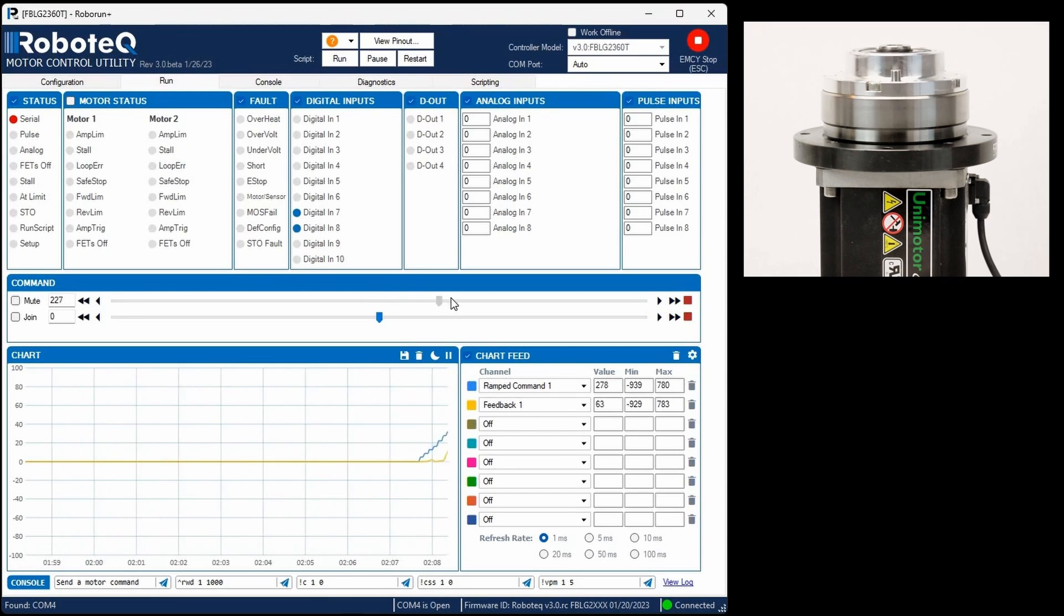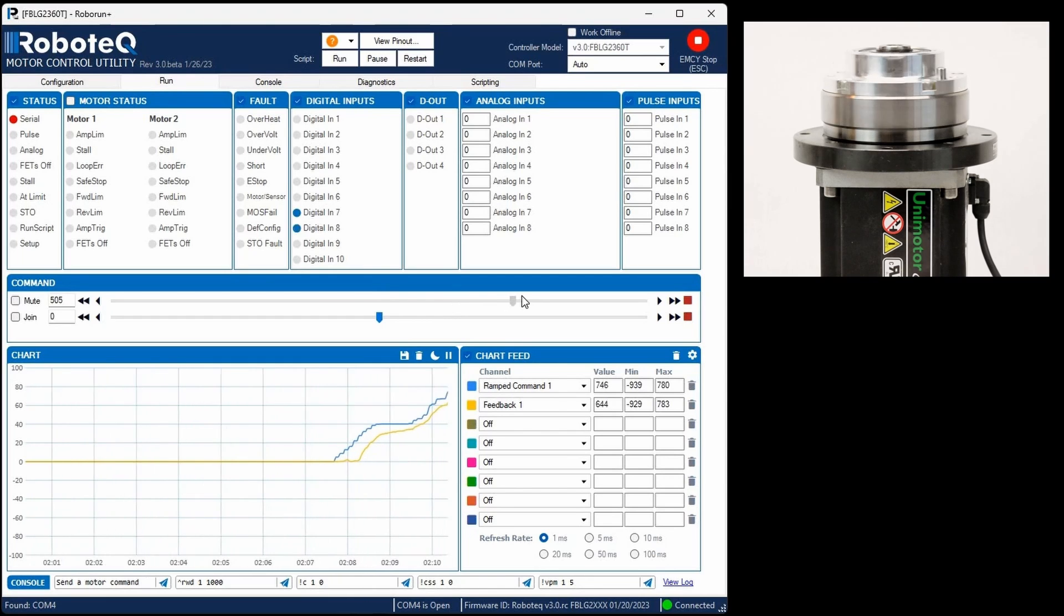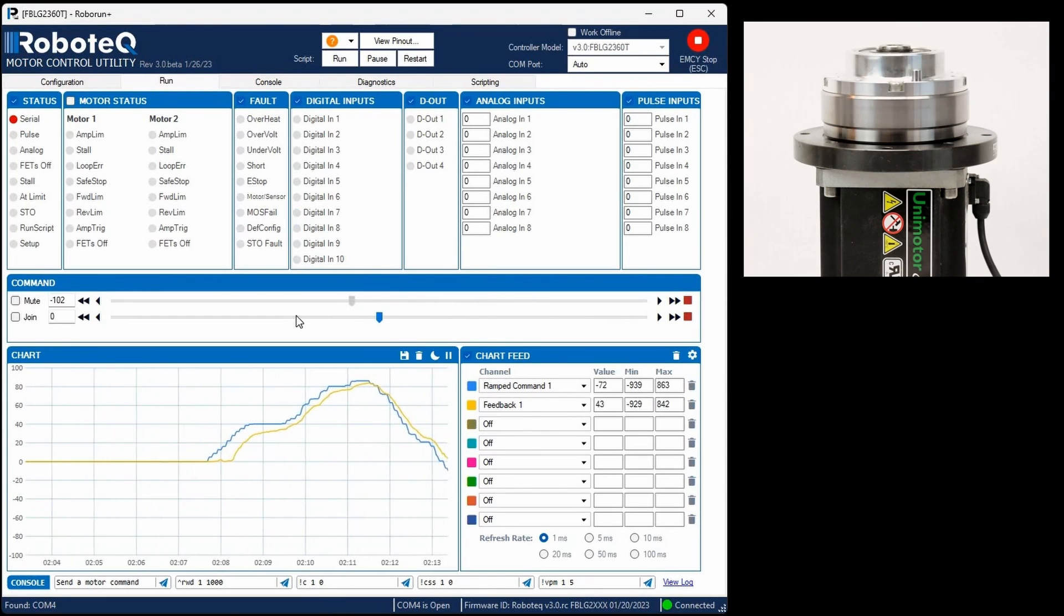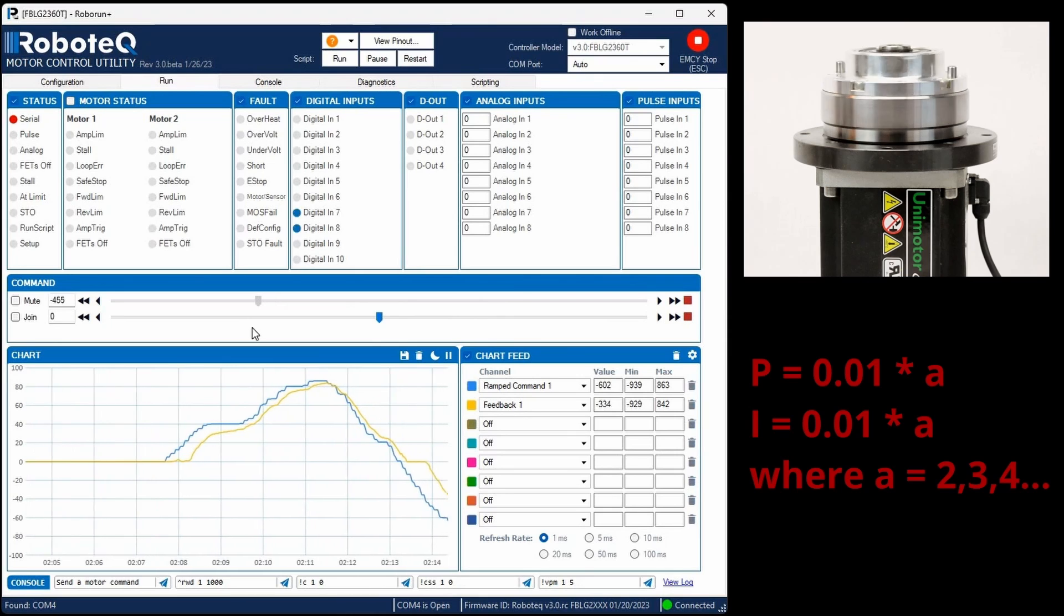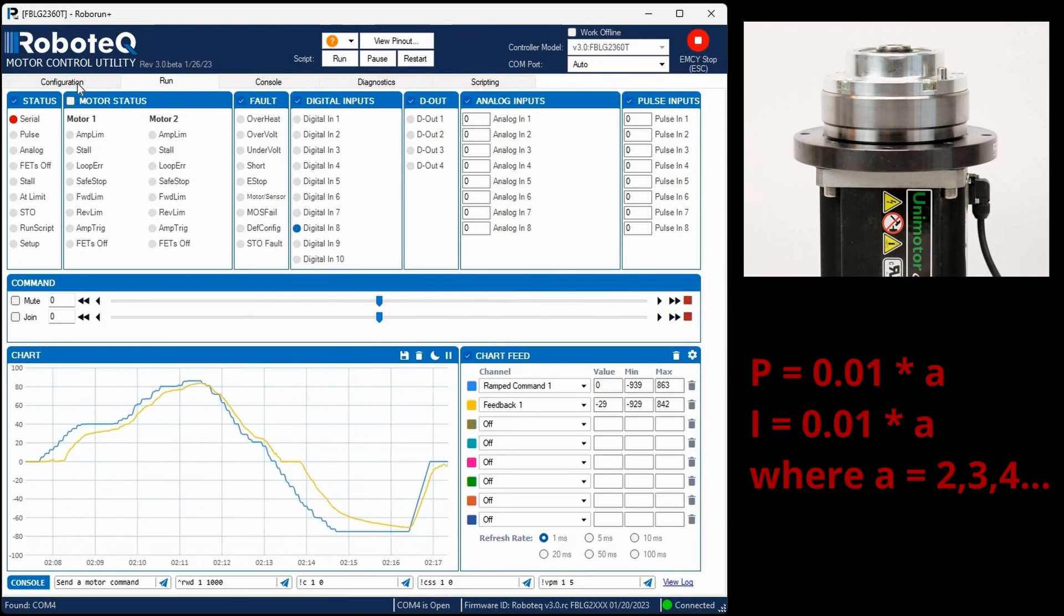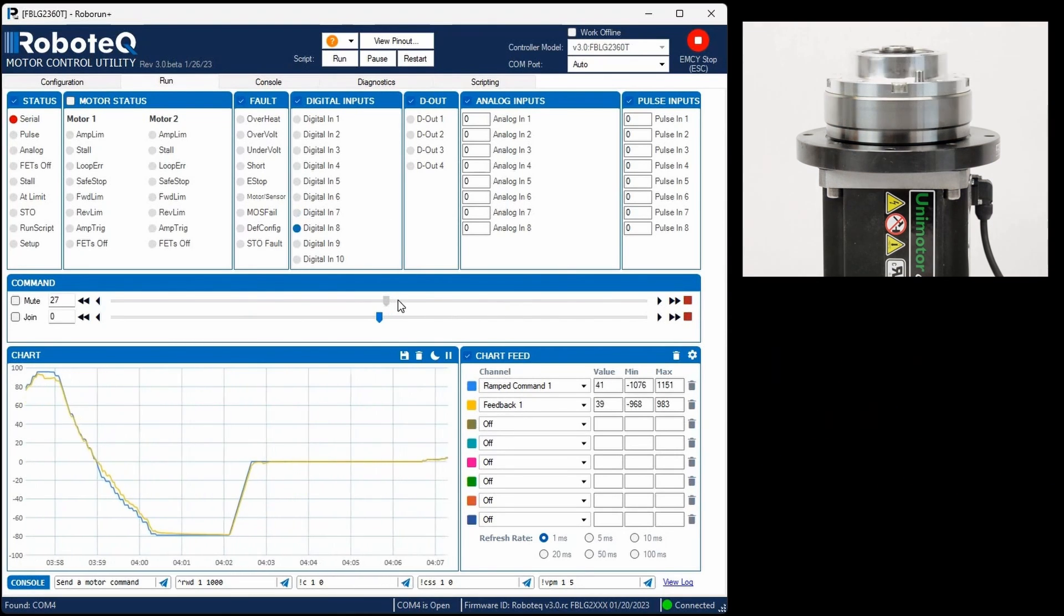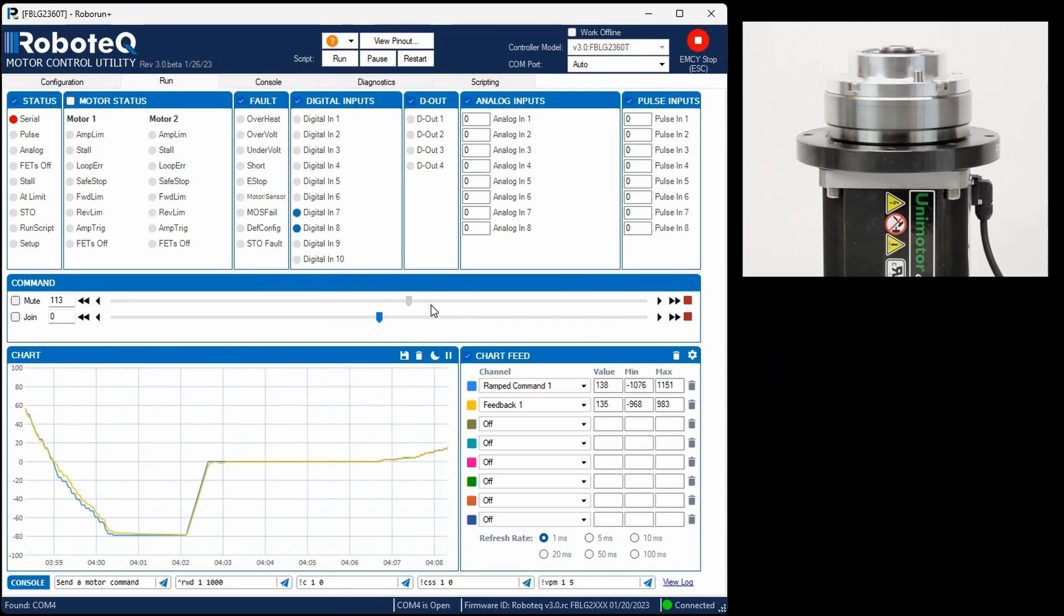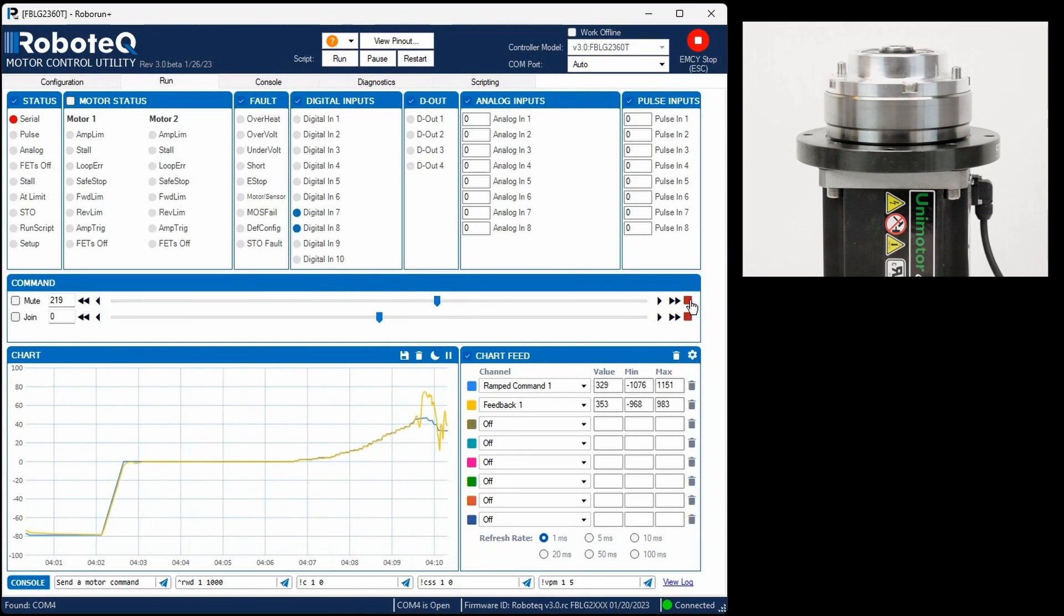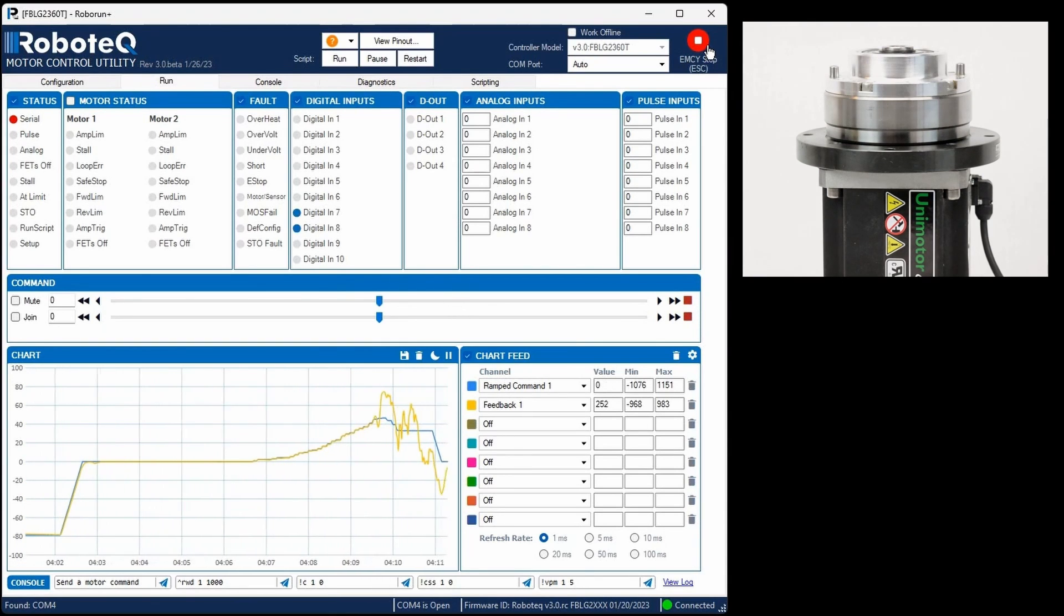If the motor response appears slow, you can increase the values of both PI gains by the same factor. Conversely, if the motor exhibits vibrations, consider decreasing these values.